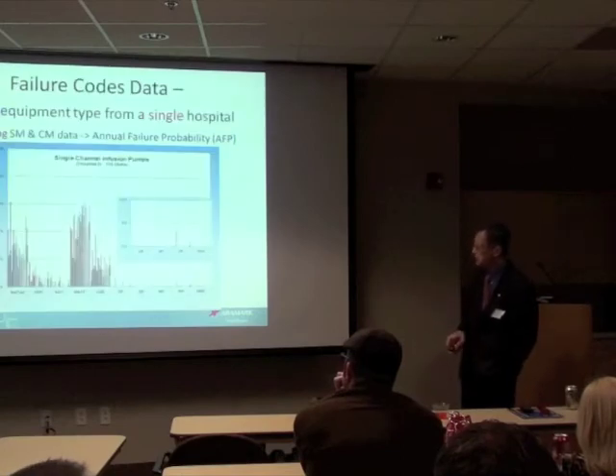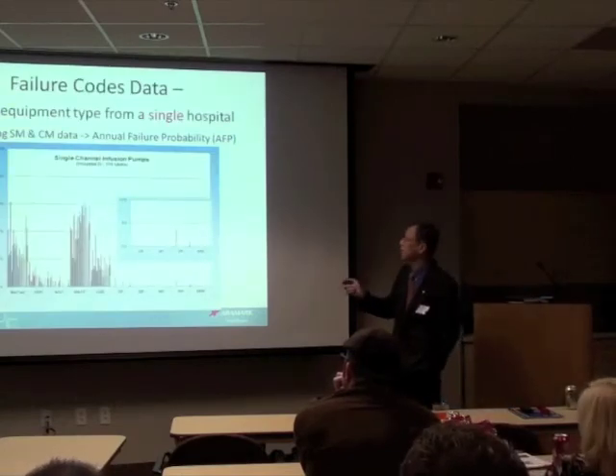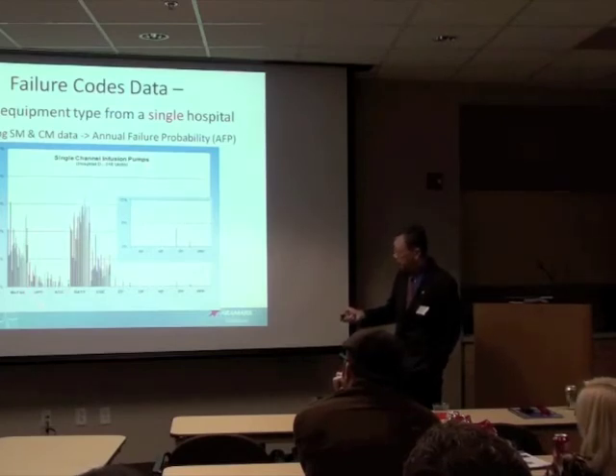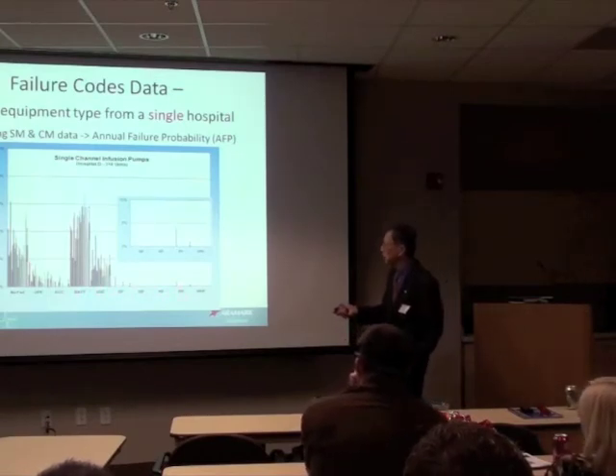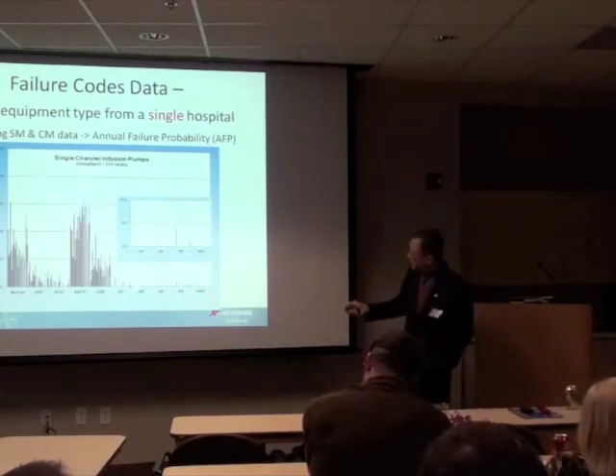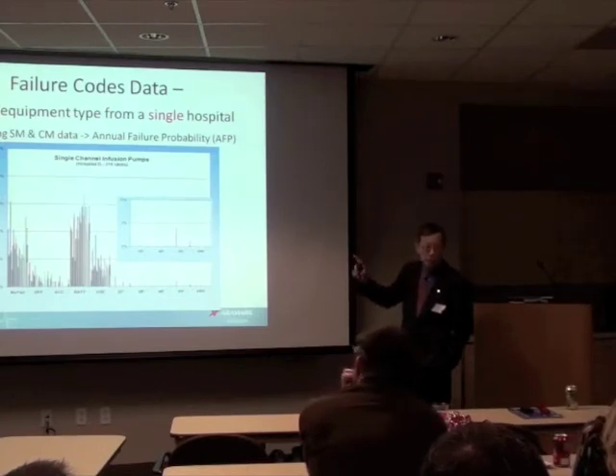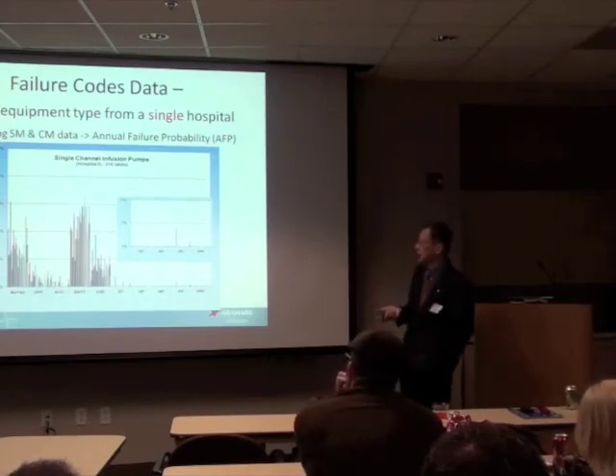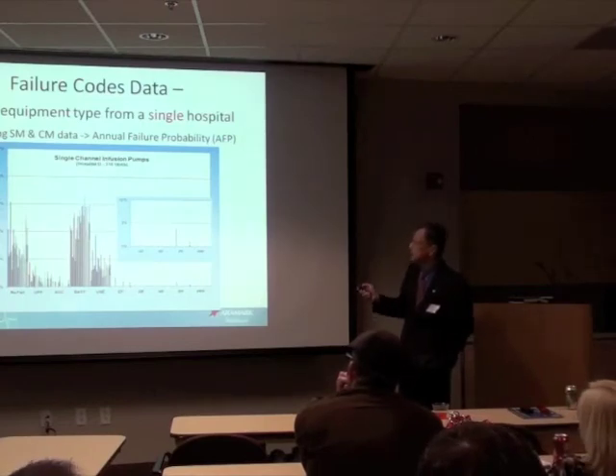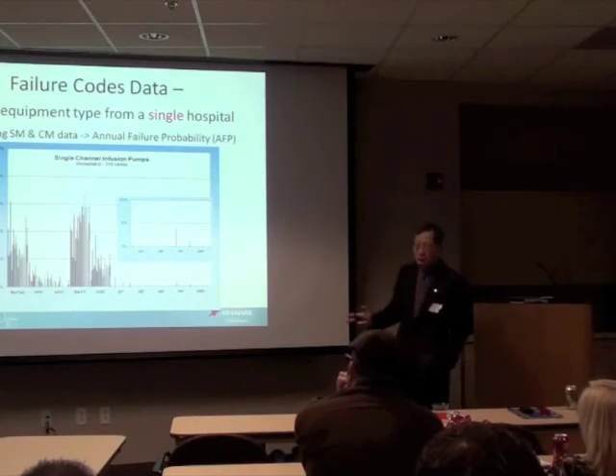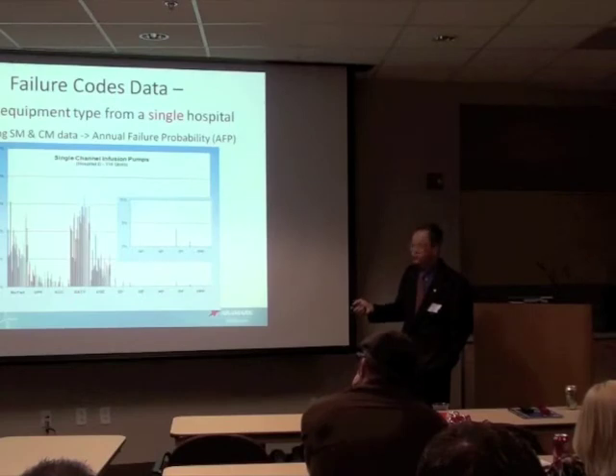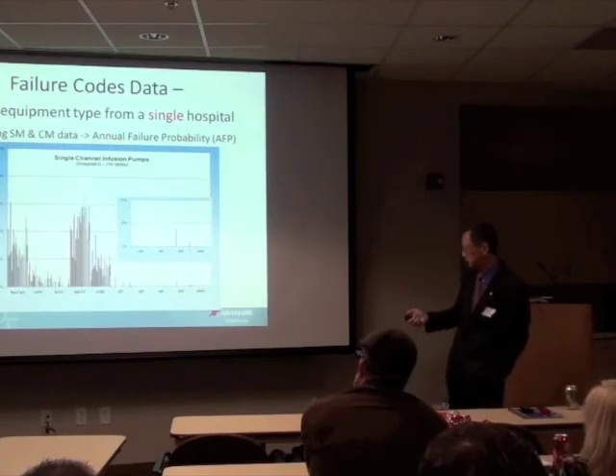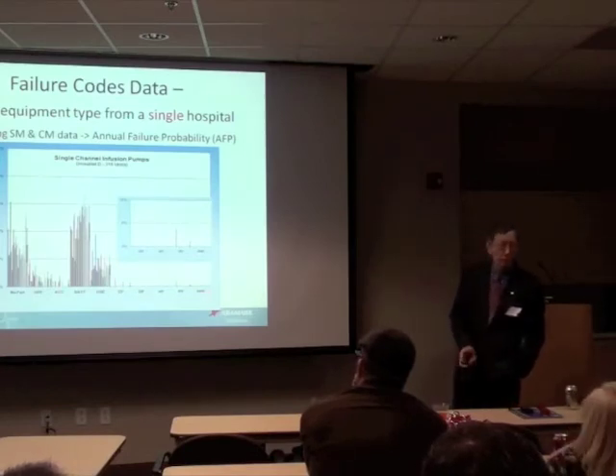If you do this exercise again with the same statistics I showed before, now combined — no failures, unpreventable failures, accessory failures, battery failures, use-evident failures, service-use hidden failures, potential, predictable, and preventable — these last four are so small I expanded the scale so you can see them. Again, this is a single hospital, same set of users, same brand and model of equipment, so it still has a lot of fluctuation, which is inevitable. But there is a tendency: most of the problems are due to battery, no question about it. Use and no-fails are second. These others aren't really that many issues.